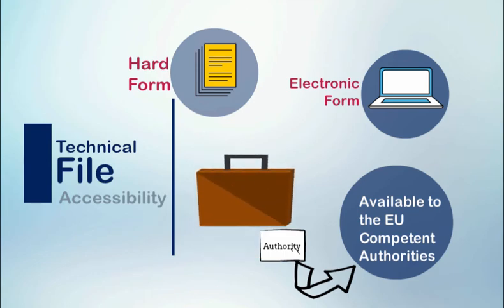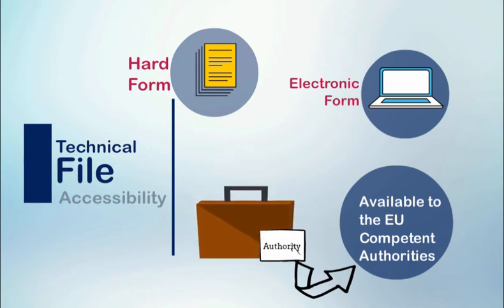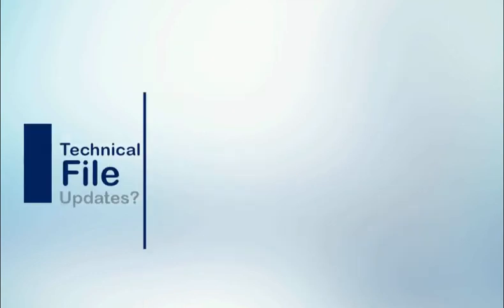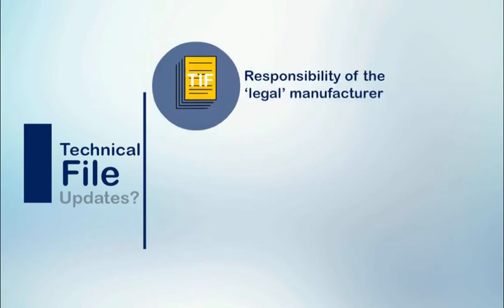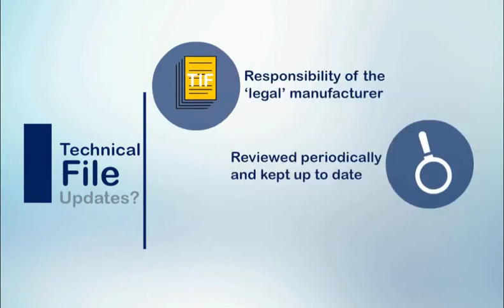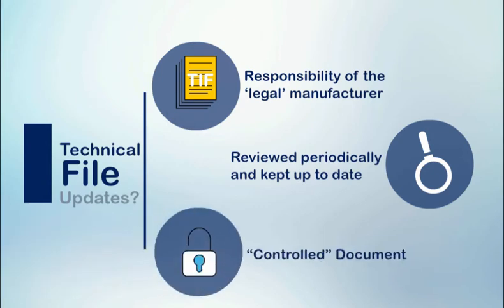It must be made available to the EU competent authorities at the registered address within the European Economic Area. As the file is the responsibility of the legal manufacturer, it needs to be reviewed periodically and kept up to date. Changes must be recorded, making the file a controlled document within the quality system.